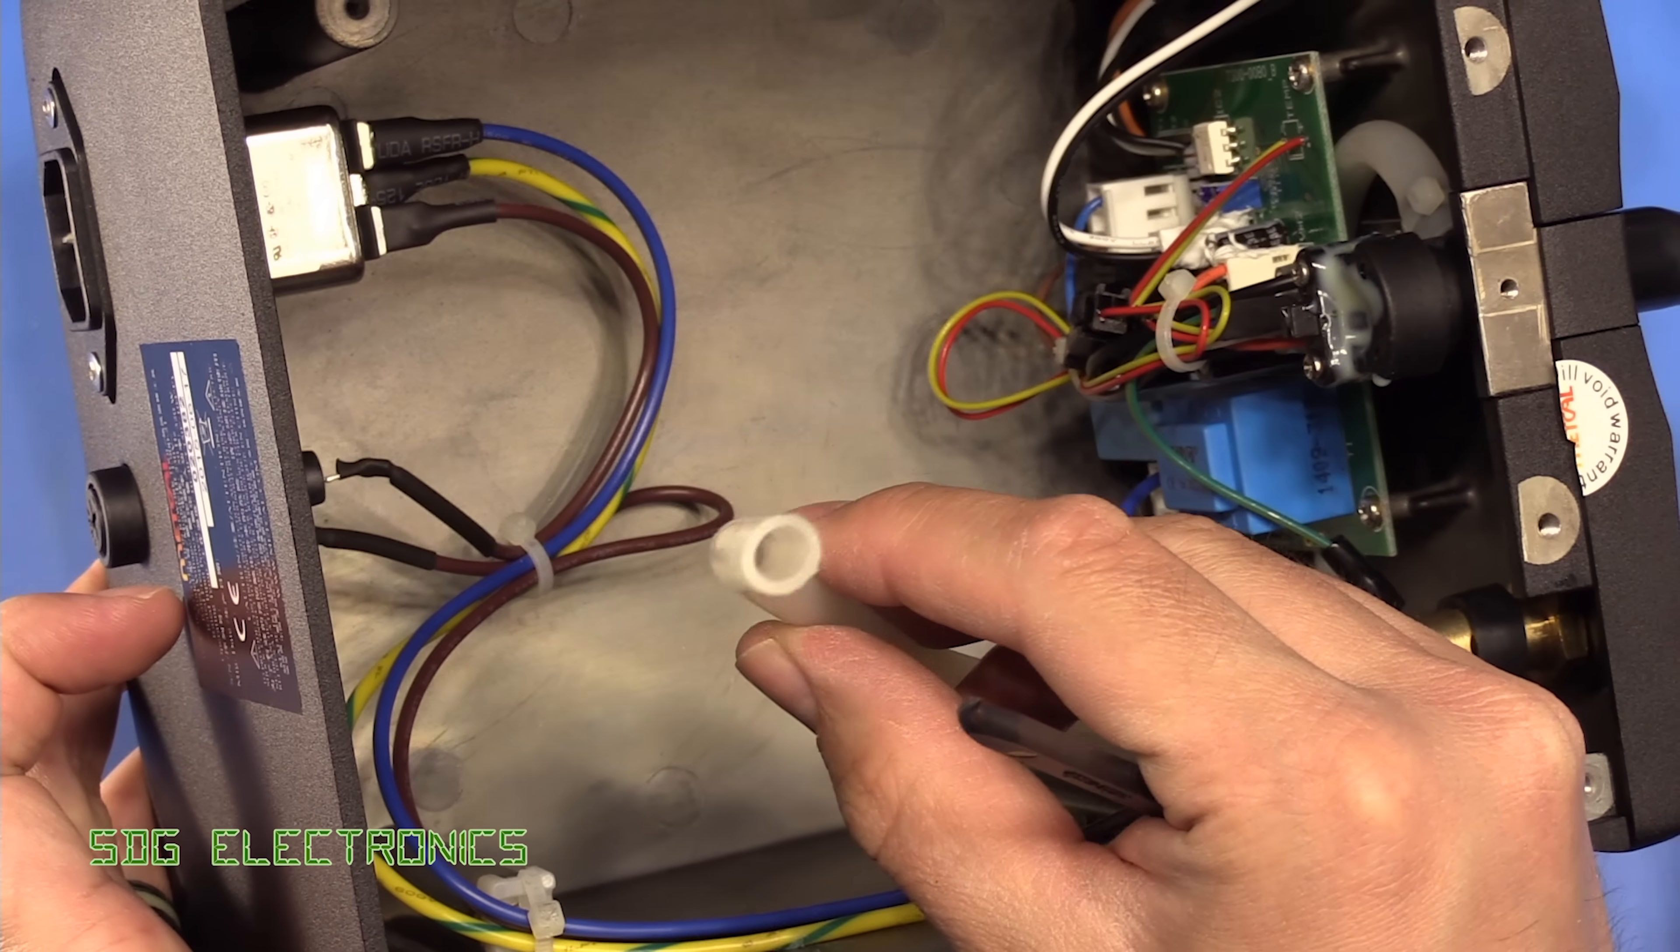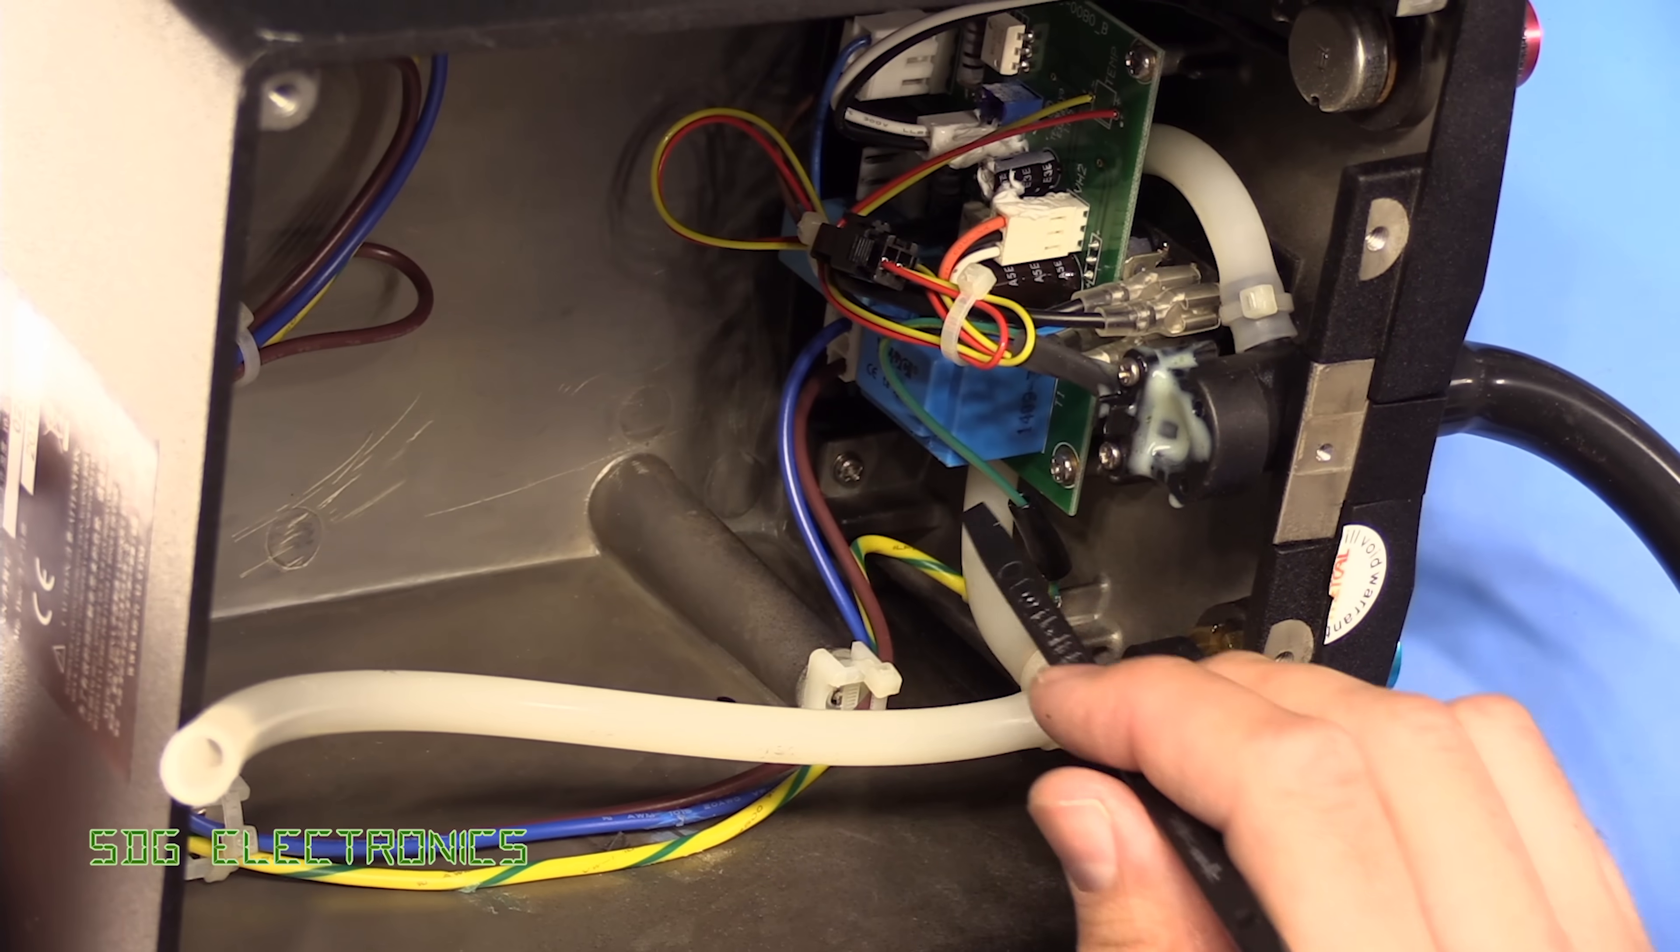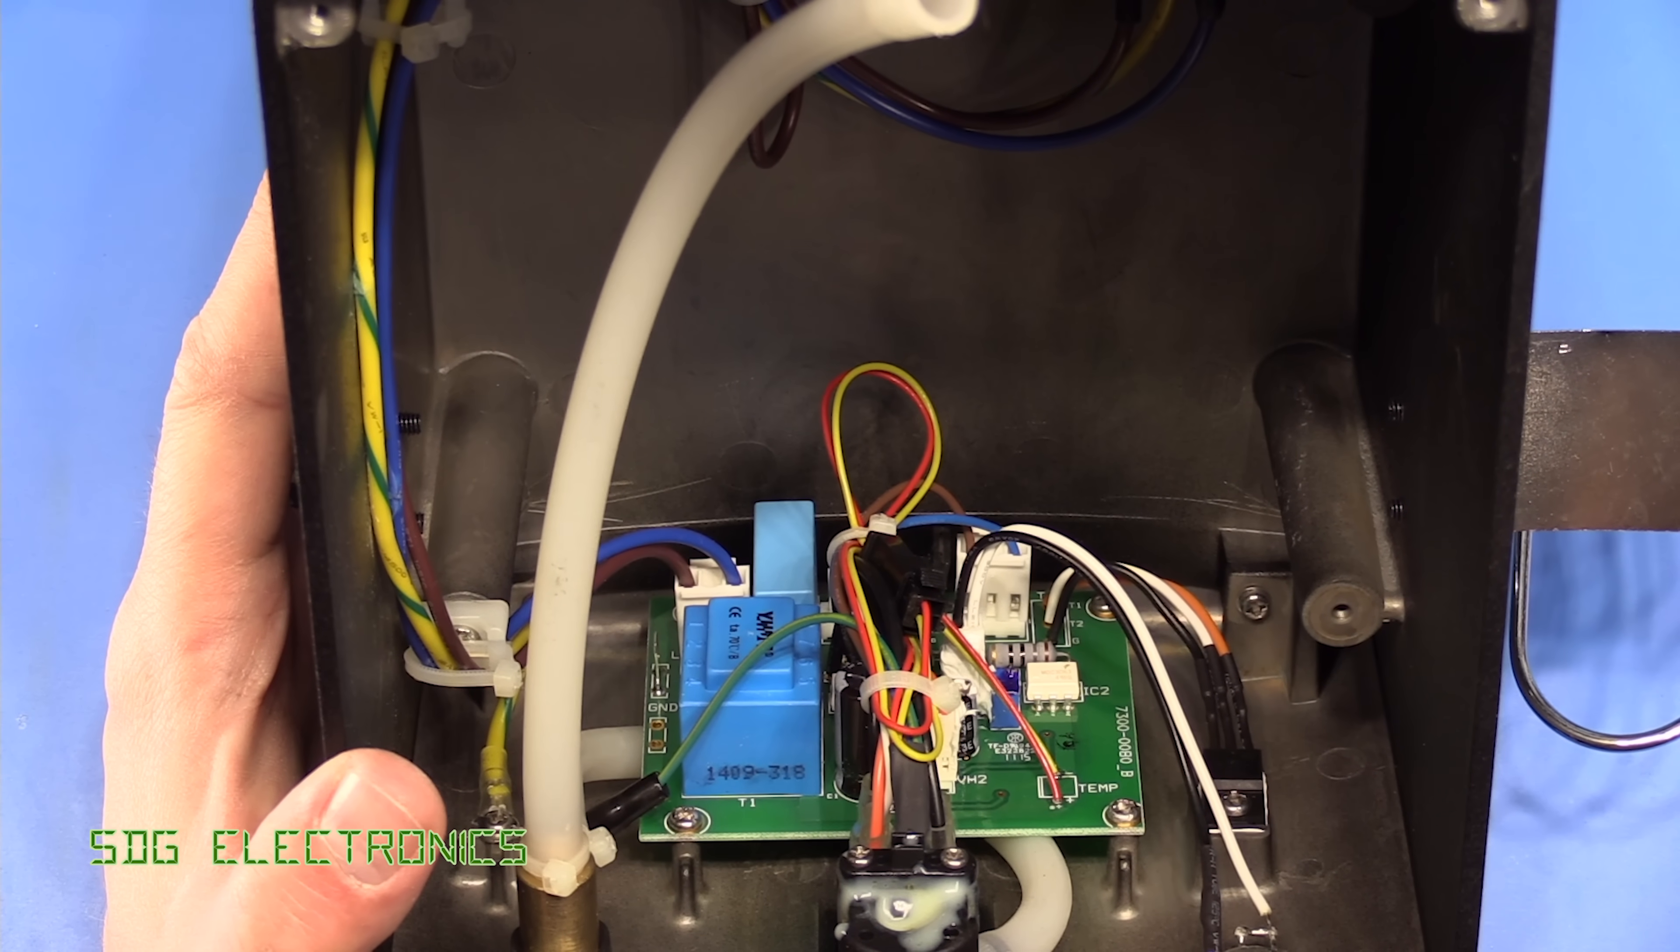Now here you can see this is the tube from the air pump. I haven't actually realized but it makes sense, I suppose. Using a diaphragm pump, the actual control on the front here, it feels exactly like a potentiometer. There's hardly any resistance, but it actually just restricts the airflow through to the handpiece. So that does make sense and it's a very simple mechanism, so just simply a valve that opens and closes to change the airflow to the handpiece.